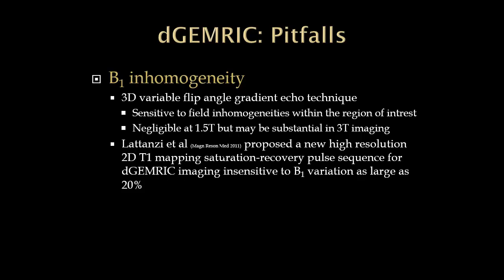Another potential pitfall is B1 inhomogeneity. If using a 3D variable flip angle gradient echo technique — as we use at our institution — it's fine at 1.5T, but moving to 3T introduces sensitivity to field inhomogeneities within your region of interest. It can still be done, but you must tweak your protocol carefully to account for these inhomogeneities. A paper in Magnetic Resonance in Medicine in 2011 proposed a new high-resolution 2D T1 mapping saturation recovery pulse sequence that was found to be fairly insensitive to B1 variation as large as 20%, which may serve as an alternative.